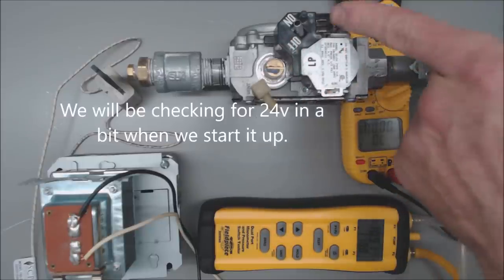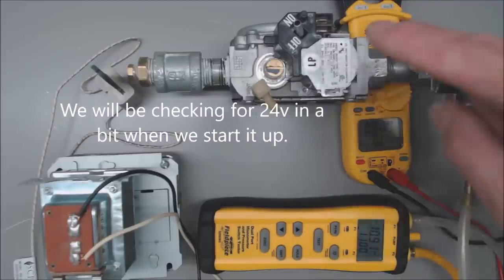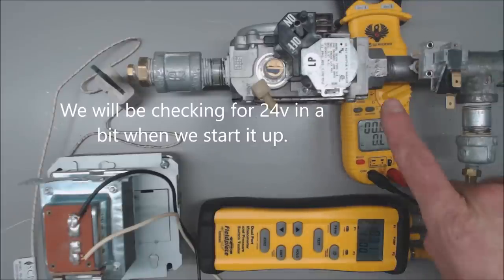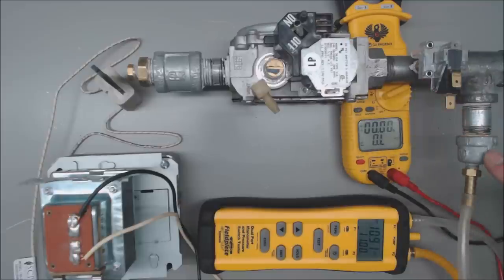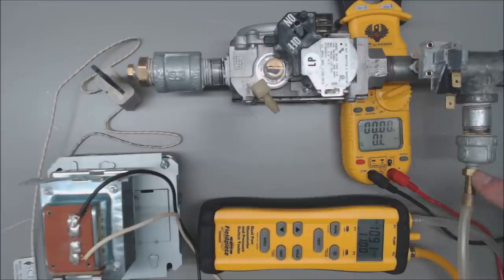On some gas valves you can check the resistance value, but on this one what we're going to do is read the inlet gas pressure right out of this cap right here. The easiest way to read the incoming gas pressure is to just have, say, a half inch cap already with an eighth inch brass fitting attached to it, and then maybe also have a three-quarter and maybe also a one inch in the truck that's already tapped with this barb fitting on it.